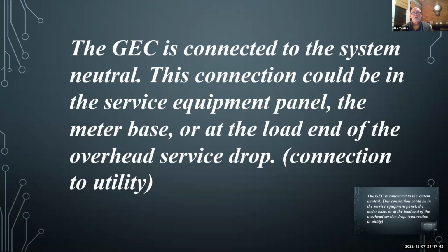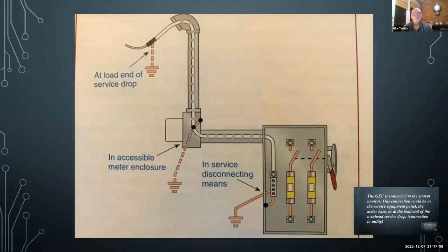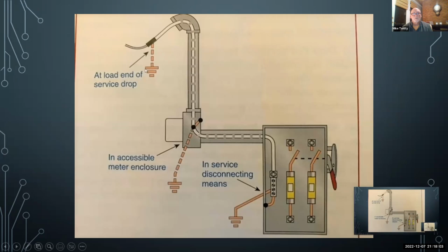Okay, we discussed that. The grounding electrode conductor, GEC, is connected to the system neutral. This can be done at the service equipment panel, the meter base, or at the load end of the overhead service drop. I've got a graphic showing that. You can make that grounding electrode connection at any of these three places. You're not going to see it at the drop too often, but it can be connected there, and then it's going to follow the building down and go to the ground rod.